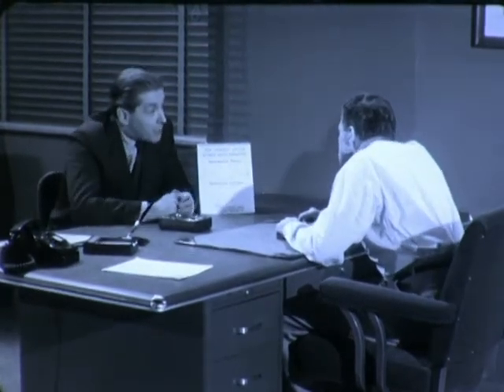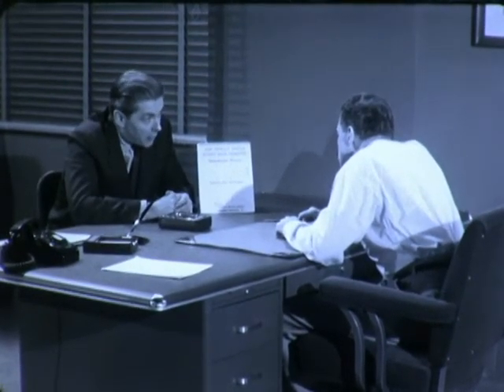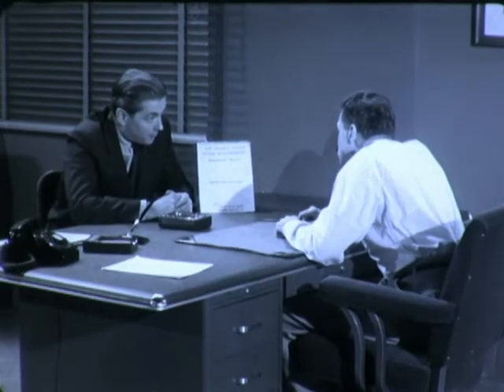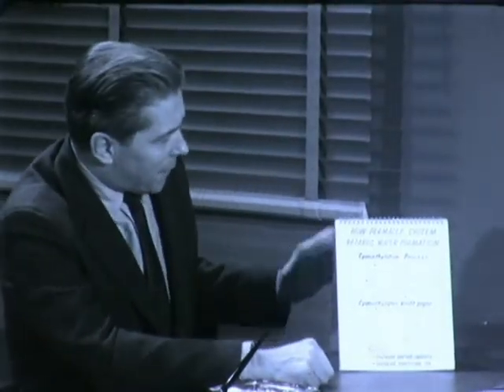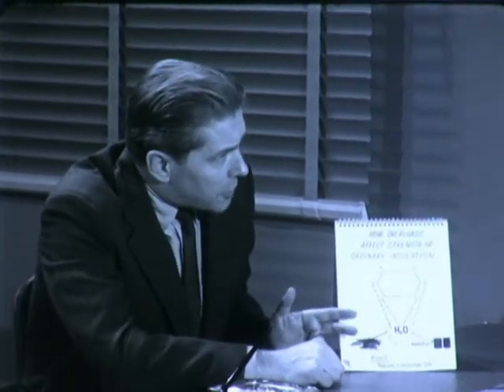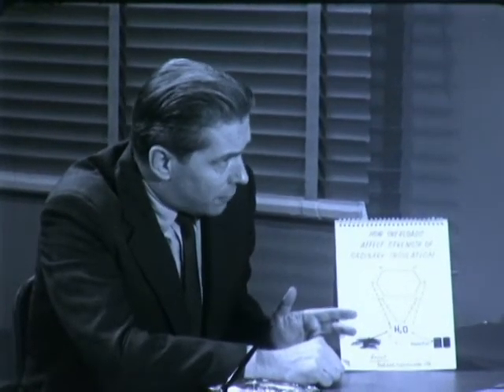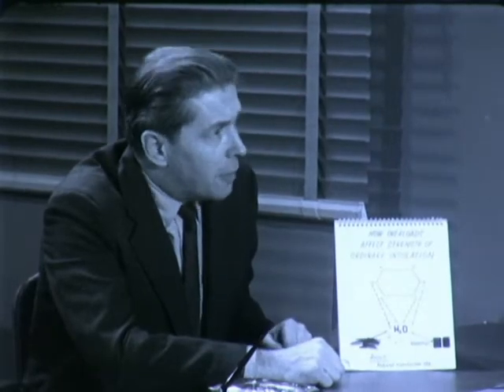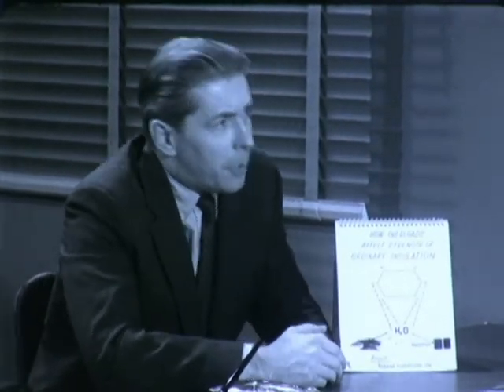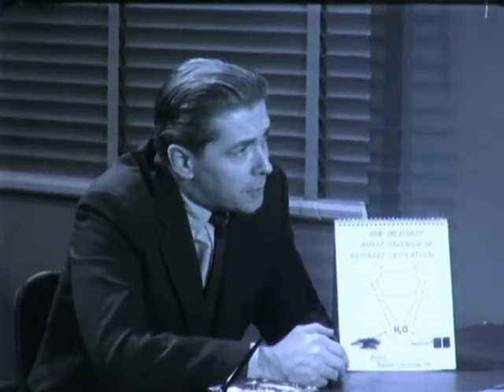This retards the aging of insulation during overload, and in return reduces operation costs. For instance, with ordinary insulation, overloads cause water and sludge formation in the insulating oil, a major factor in reducing transformer life. Permalex retards this water and sludge formation and results in 20% increased loadability with no change in life expectancy, and gives you 5 times longer transformer life at present loads, or a combination of both.